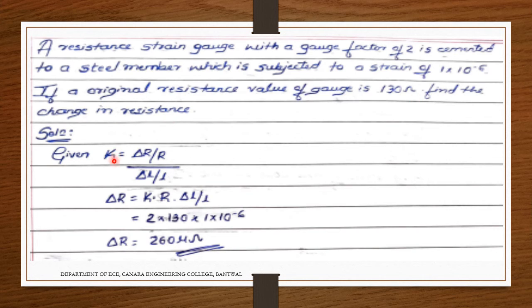So what is the strain gauge formula? K equals delta R by R, divided by delta L divided by L. We need to find the change in resistance, delta R. Rearranging the formula: delta R equals K into R into delta L divided by L. The gauge factor K is 2, R is 130 ohms, and delta L by L is the strain, 1 into 10 to the power of minus 6. By simple substitution, delta R equals 260 micro ohms.